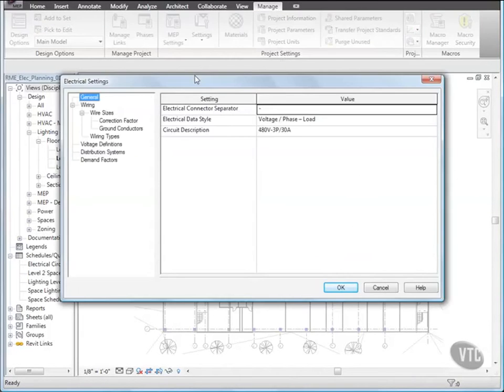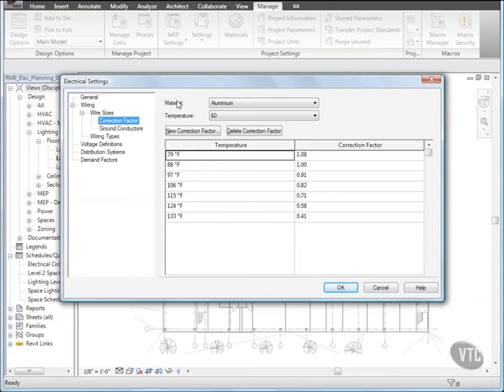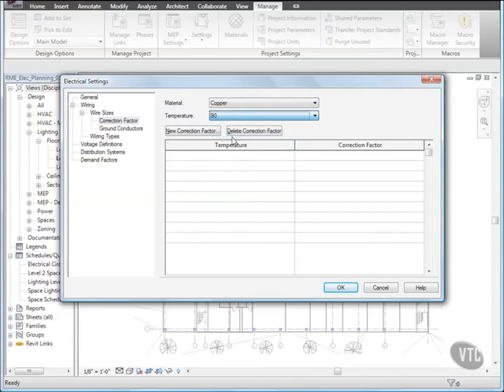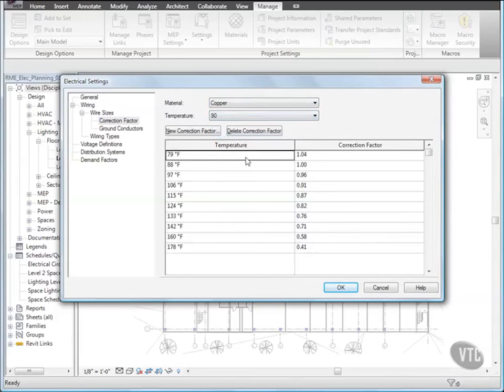In the Electrical Settings dialog, select Correction Factor, and for Material, select Copper, and for Temperature, select 90, and click New Correction Factor, and for Factor type 1.04, and click OK.